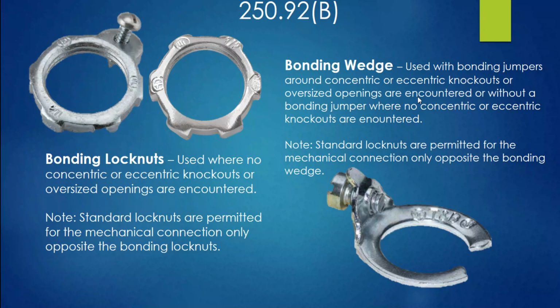Now, what about bonding wedges? The use of bonding wedges is for where concentric, eccentric knockouts or oversized openings are encountered. You can use these, okay? But where you do encounter it, then you need a bonding jumper. And you can utilize these with the bonding jumper. All right. Now, where there's no concentric, eccentric knockouts, then you don't need a bonding jumper, and you can drive this into the raceway, into the nipple, and then you'll have a bonding bushing or a bushing on top of this, or another standard lock nut on top of this, driving this tight against the enclosure. Okay. Again, standard lock nuts are permitted for the mechanical connection only, opposite the bonding wedge, but standard lock nuts are not to be used for the primary bonding purpose in this application on the line side of service equipment.